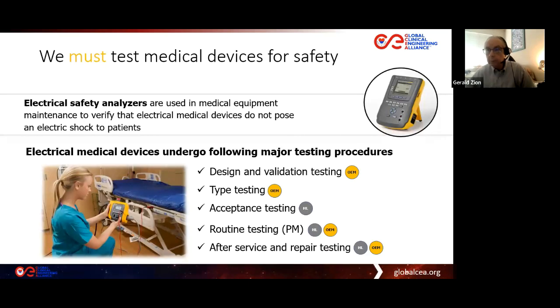All right. The places where electrical safety testing for sure is done is during design and validation testing, type testing. That is at the medical device manufacturer's location. Acceptance testing is done in the hospital or the clinical client site by us. And also we do the routine testing. The manufacturer's field service engineers will also do routine testing under contract.